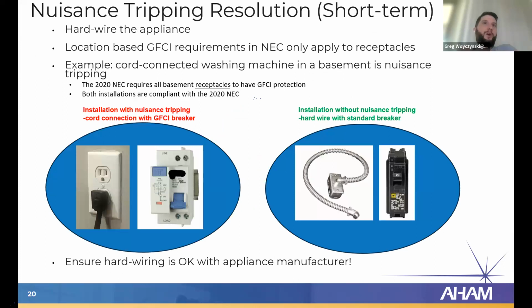The last short-term fix we'll go over is hardwiring the appliance. The location-based GFCI requirements in the NEC only apply to receptacles. Let's step through an example. Let's say you have a cord-connected washing machine in a basement that is nuisance tripping. And again, we'll use the 2020 NEC as an example because that's what's most widely used today. The 2020 NEC requires that all basement receptacles be GFCI protected. So both of these installations are allowed as per the 2020 NEC.